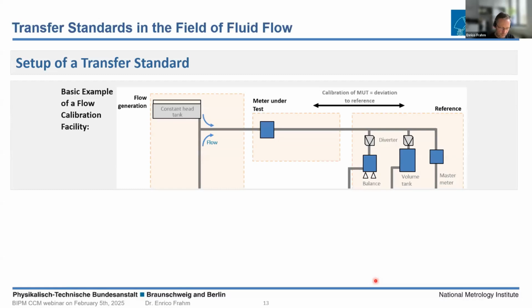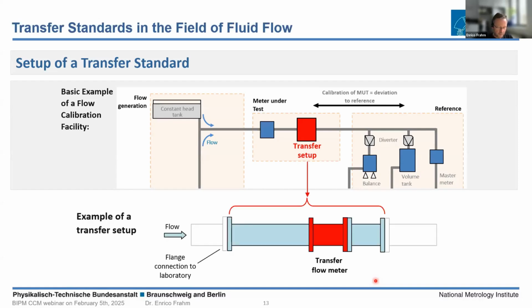So back to one of my first slides, the transfer standard will be installed, as already mentioned, at the same place where the meter under test is installed. A characteristic setup consists of the meter itself, this is the transfer meter. And an advanced setup could also include an inflow section, outlet section, and a flow straightener.